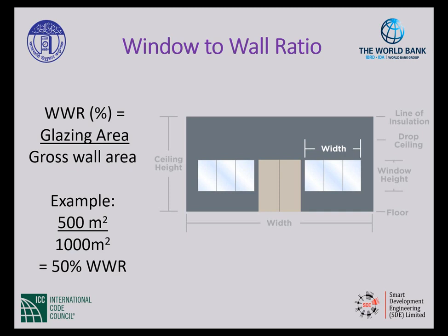Now to calculate window to wall ratio, it's pretty simple. You just take the gross area of a wall with all of its doors and windows in it. So you take the gross area, including all the doors and windows, just pretend they're not there. What is the area of that wall? Then you go in and add up the square feet or the meter square, the area of your windows and any glass doors. So regular opaque doors would be considered wall, but if they were glass doors, they would be considered part of your glazing area, your window area. So we're going to take the wall area and then add in the window area.